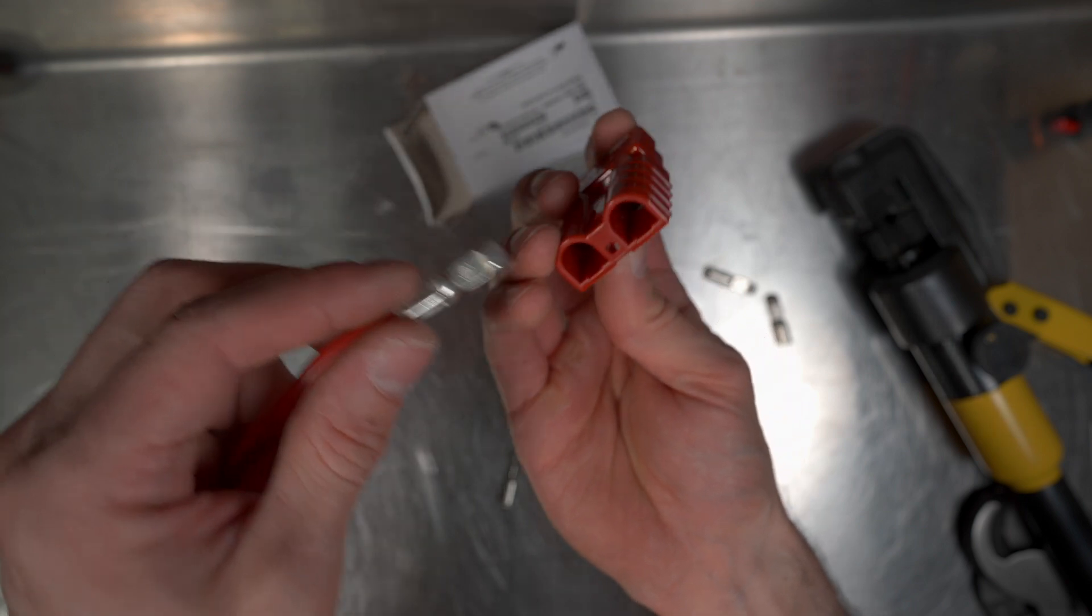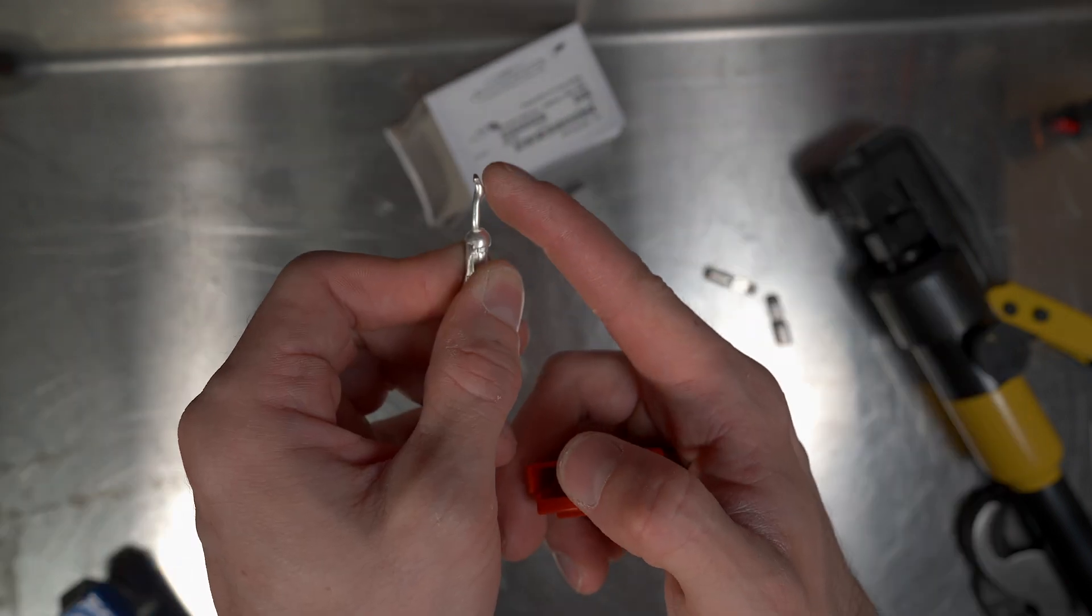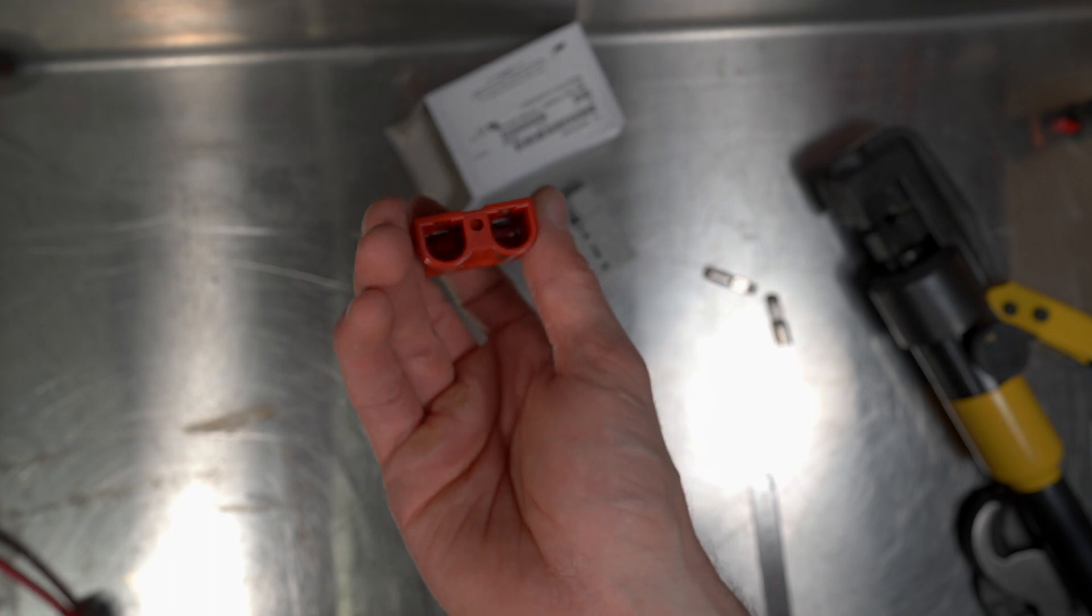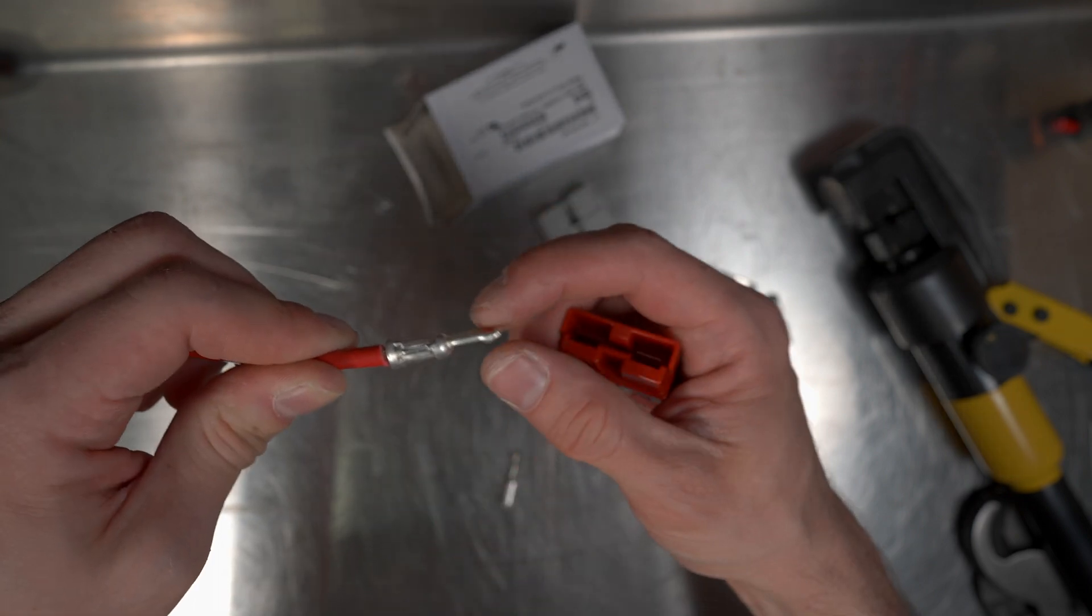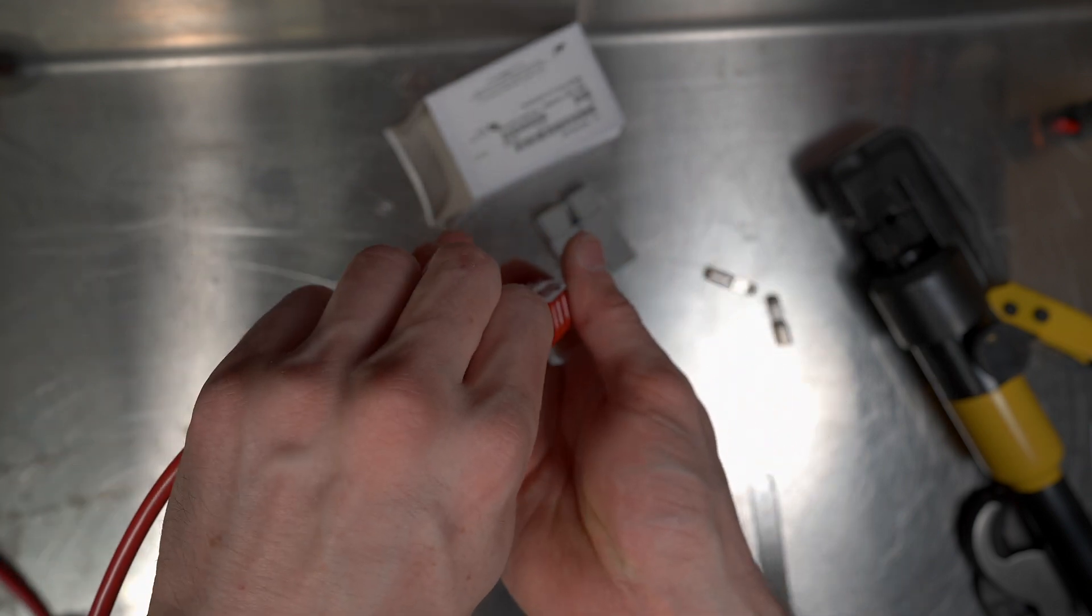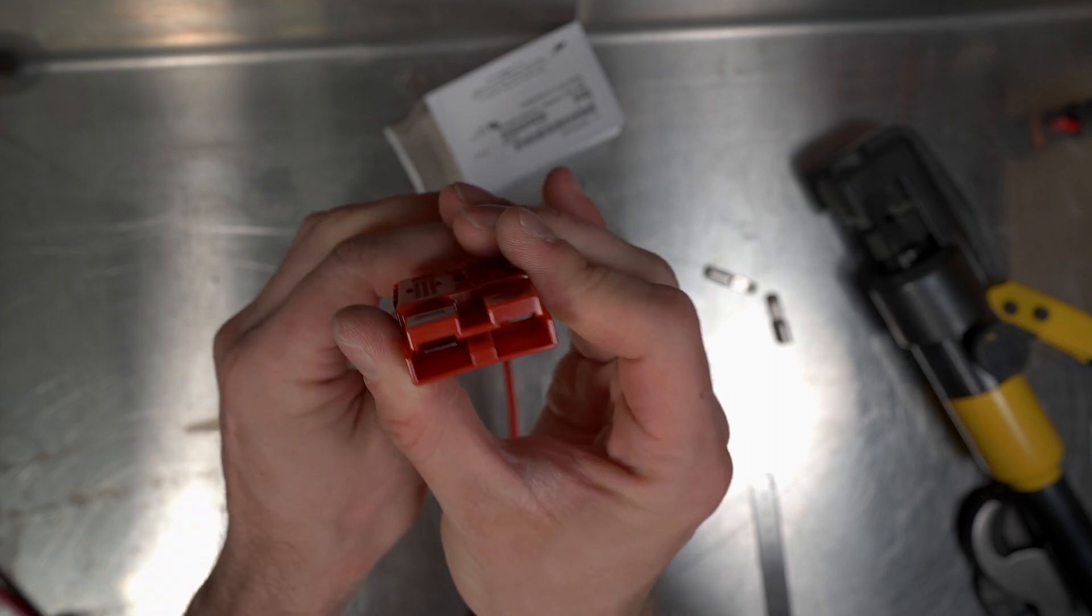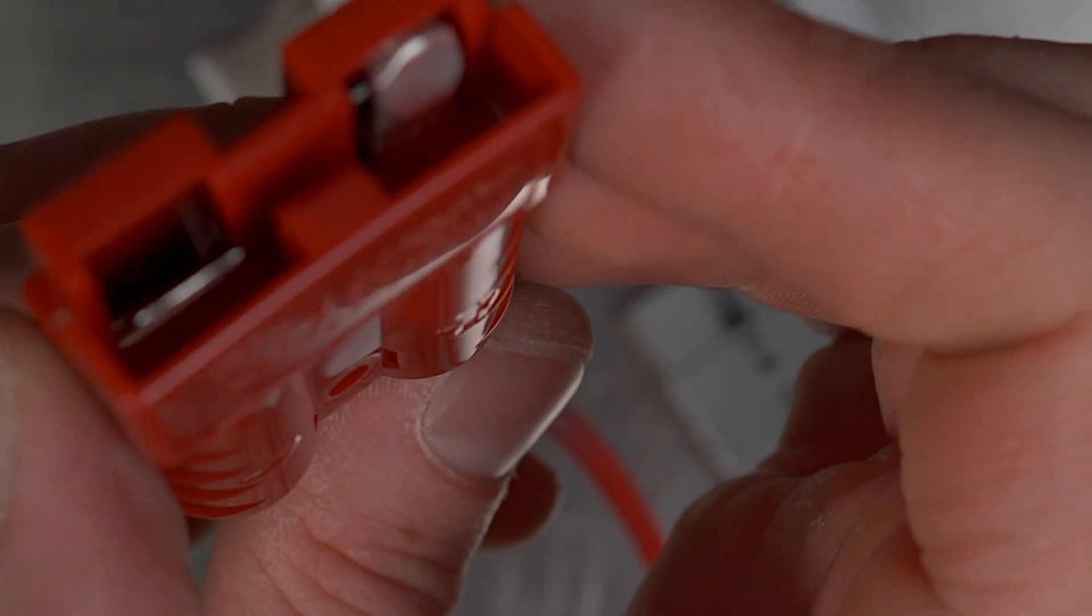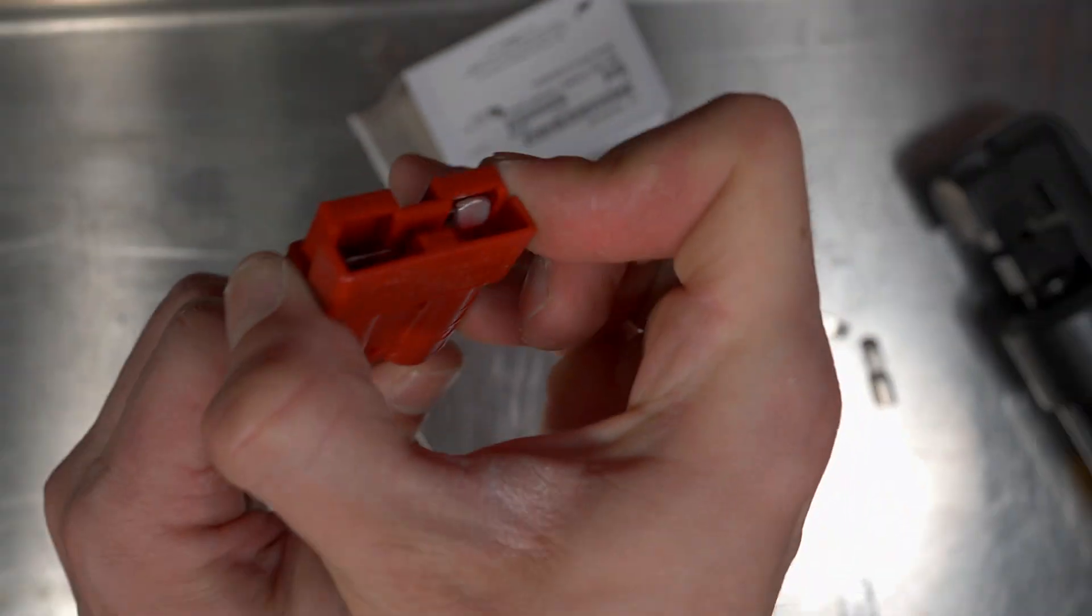Once the cable is lugged, you can push it into the terminal, remembering that the bump is facing down, so making sure you have the right polarity. You can see your spring tension. We push this little lip up against the spring tensioner so it clicks in, and there you have a solid click. You can see how that is clicked in with that bulge facing downwards. It is unable to be pulled out, the cable.